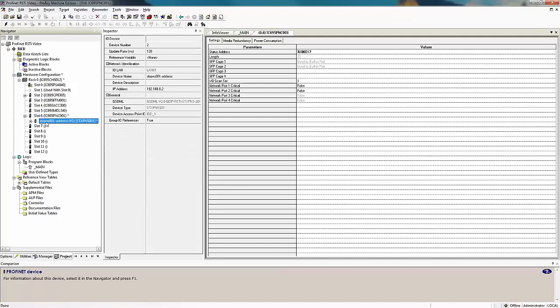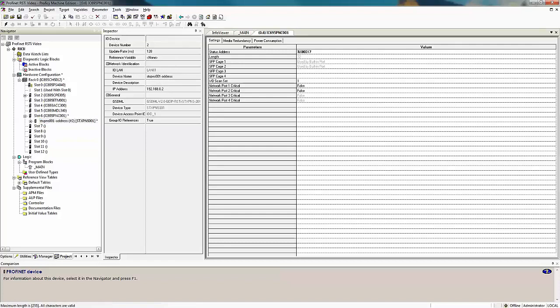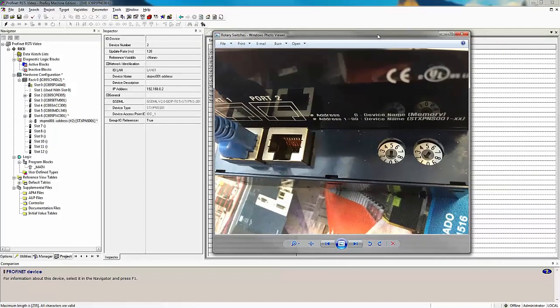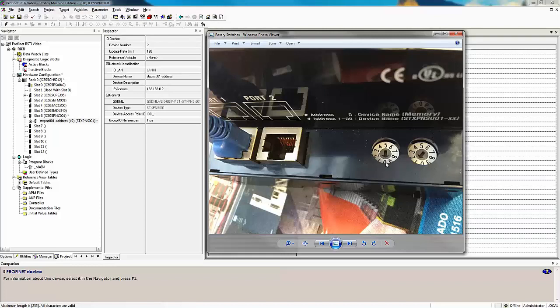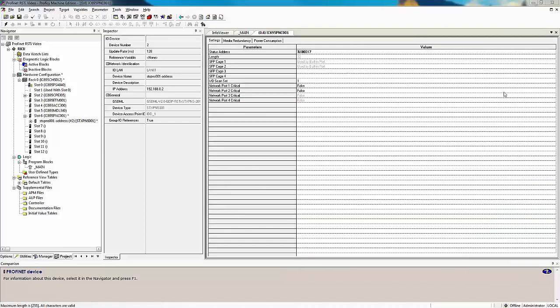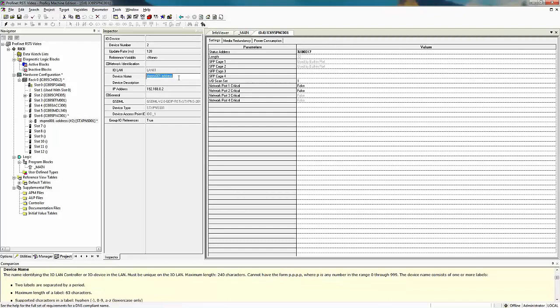If I click on my scanner, you'll notice up here under the device name, it comes up by default as STXPNS001, the model number, and it says dash-address here in the field. Now what is the address I need for my device? If you look at this photo I have here of a PROFINET scanner, you can see I have two rotary switches and the dash-address will be these rotary switches. In my particular example, I have 0 and 1. So now that I see my address is 01, I can go back to the device name and add the 01 here to my address, which provides the name to my PROFINET scanner.